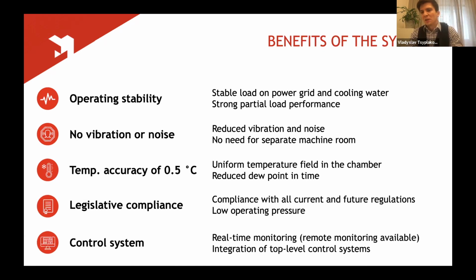Operating stability is also an important point, because the machine is continuously operating throughout the whole cycle. There are no peaks on the power grid and on the cooling water. This usually happens in freeze drying cycles when there is a huge cooling demand. You have a peak load on the water circuit. We don't have vibrations and no high noise. This is a feature of centrifugal compressors. There's a low noise feature, and you don't need a separate machine room for the installation of our units.